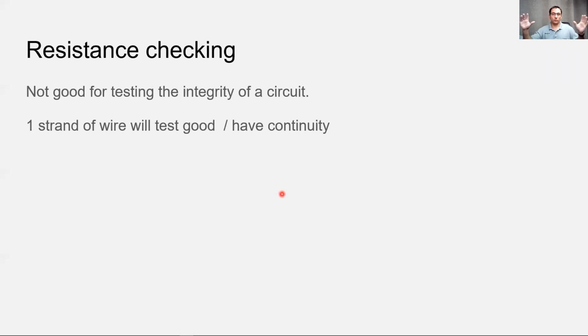How many times do you see a flow chart that tells you to disconnect this end and that end, disconnect the computer and the sensor, measure the resistance on that circuit, and check if it reads less than 5 ohms, or less than 2 ohms? And here we are: the resistance is within specification, but when we have to load that circuit, or current has to flow through it to, say, turn on a purge valve, it can't handle it, and then we have a problem.